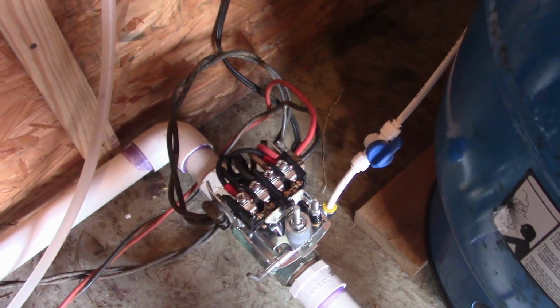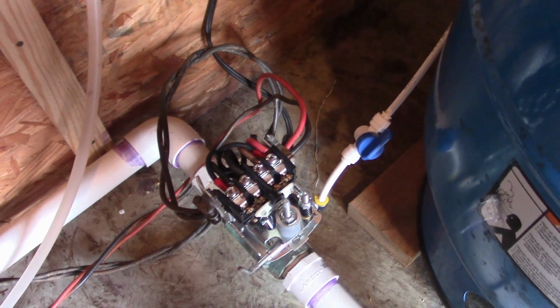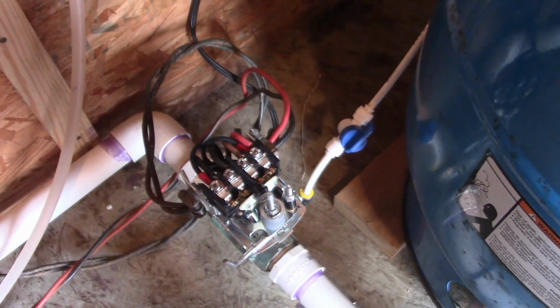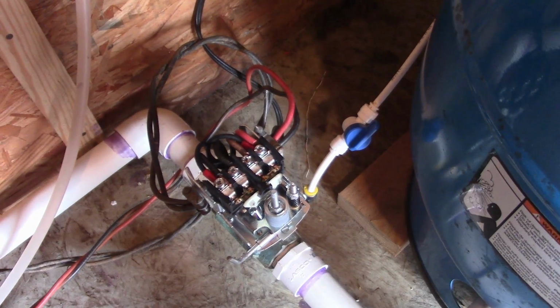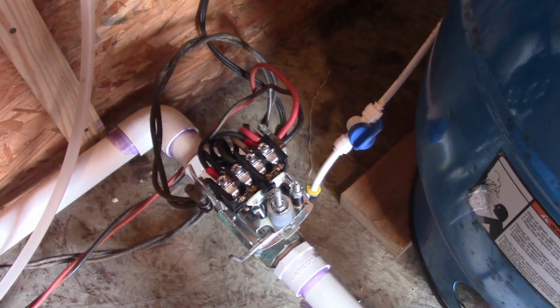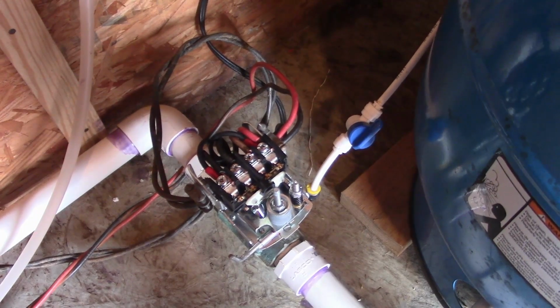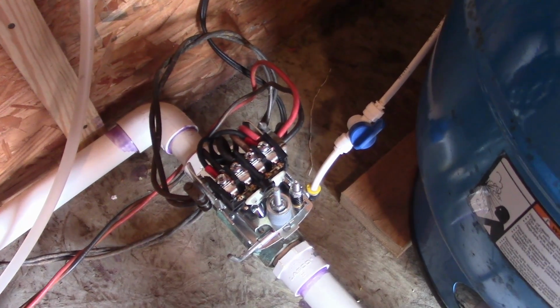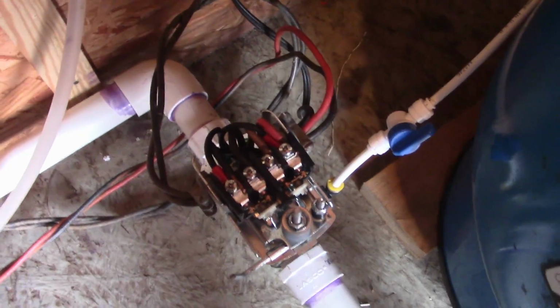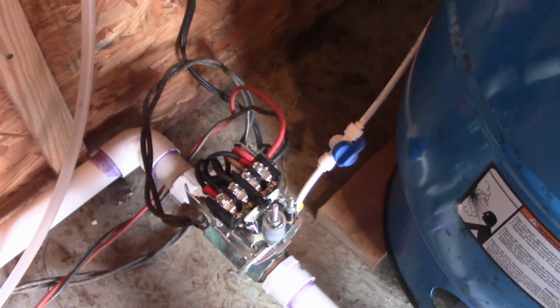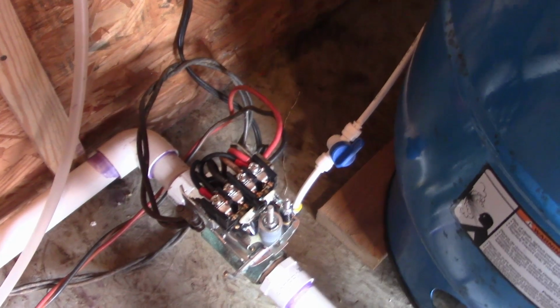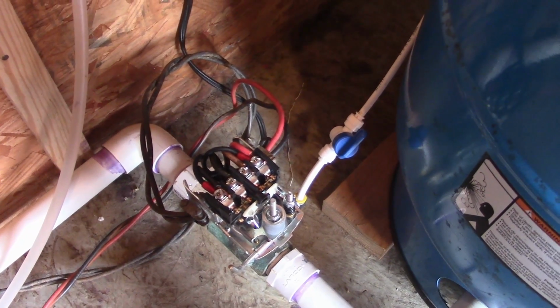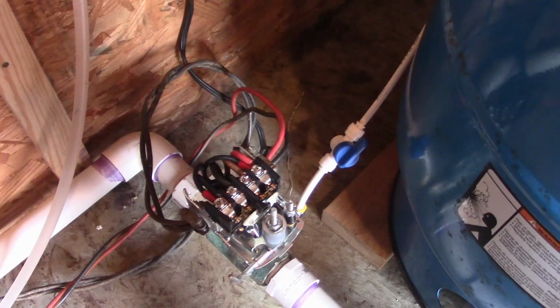I wanted to show you an alert system that I put on my pump to let me know how often it's running, and to also let me know if the pressure gets too low, like if I have a totally burst line or the pump goes out or something like that. It actually saved me the other day. A line broke in my barn and my barn was getting flooded with water, but I noticed that the pump was cycling over and over, and so I knew I needed to do something about it.